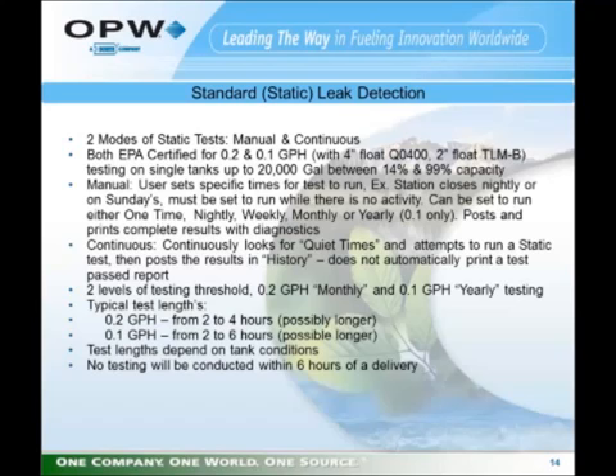If you have the system programmed for continuous static leak detection, if it performs a test and the result is a pass, it will store that passed result into history but will not print it out. If the test result is an inconclusive, it will launch a second test. If the test result is deemed to be a fail, it will print out the fail, issue an alarm, and again begin a second test after the fail.